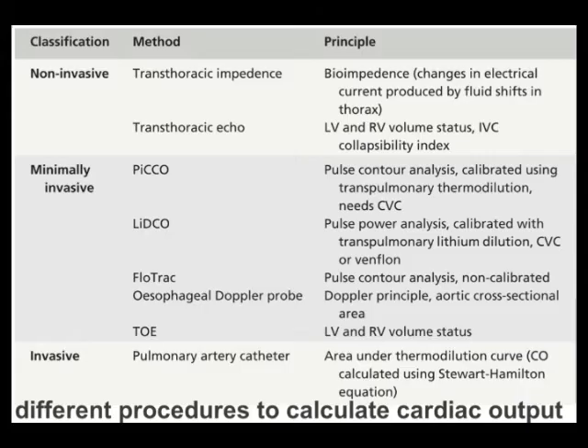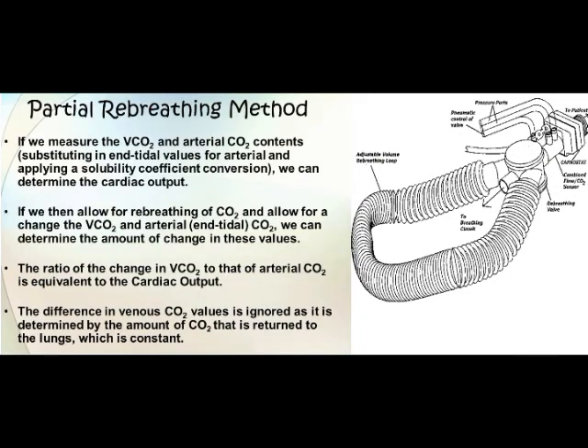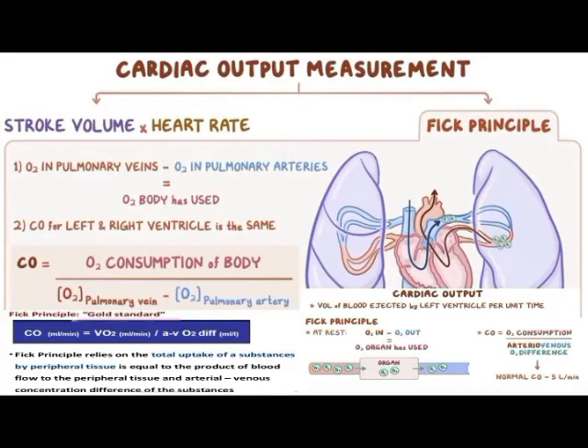Partial gas rebreathing, also known as the NICO system, uses a partial gas rebreathing monitor and the indirect Fick principle to calculate cardiac output. It is used in intubated patients under mechanical ventilation. Adolf Eugen Fick in 1870 first described measuring cardiac output in humans by calculating that the total uptake or release of oxygen by the lungs is the product of blood flow through the lungs and the difference in arterial and venous oxygen content.